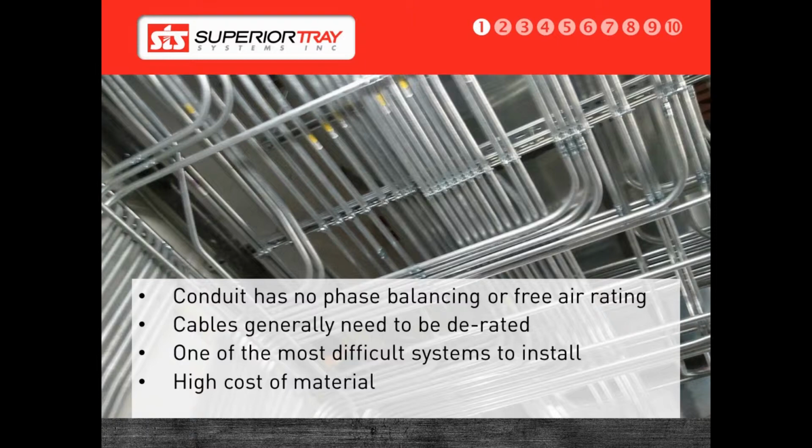In order to install a pipe and wire system, the structure first needs to be built, then the entire conduit connected together, and then the cables physically pulled through the conduit. A pipe and wire system is extremely labor-intensive and costly to install. Another issue with pipe and wire is that if a conduit travels from an outdoor environment to an indoor environment, there is no way to ensure a weatherproof seal to stop water from penetrating or running down the conduit.